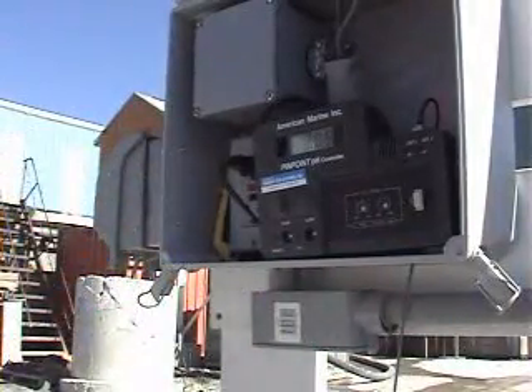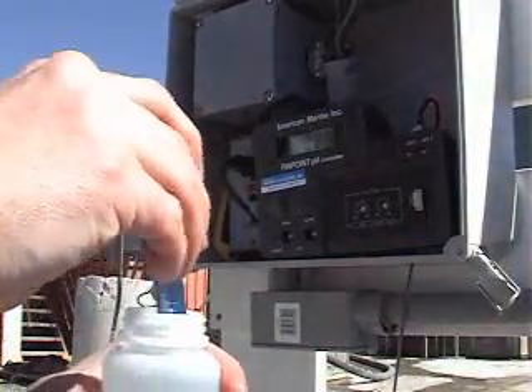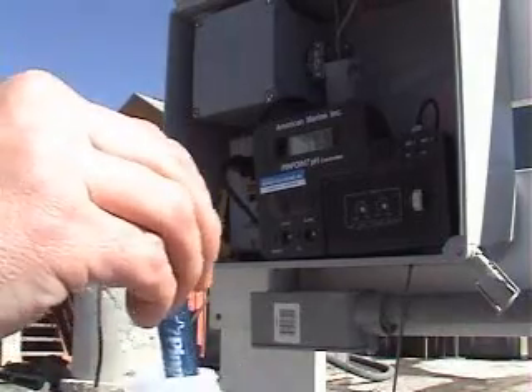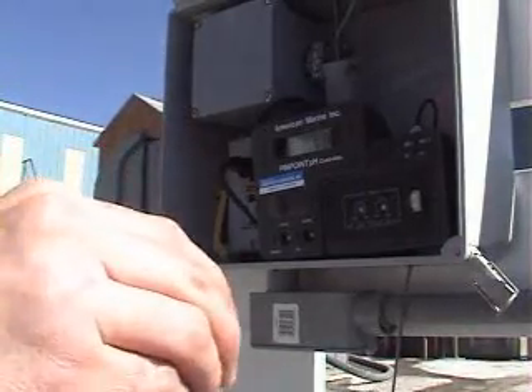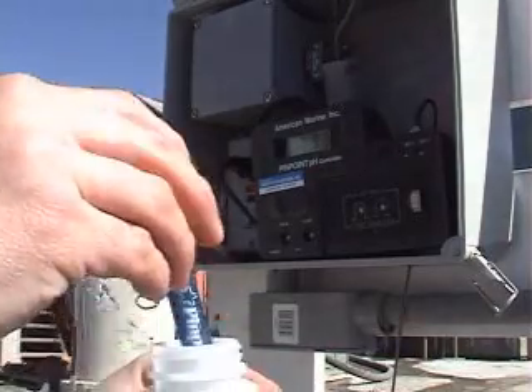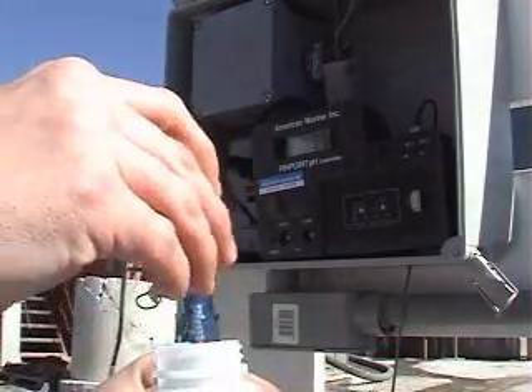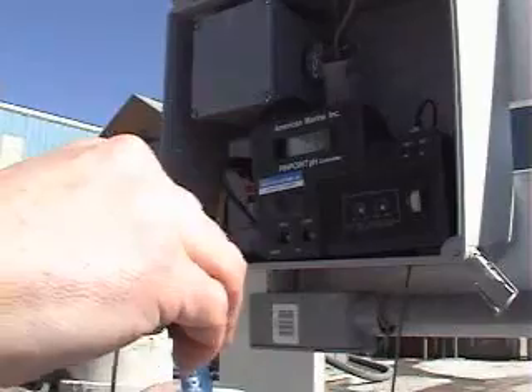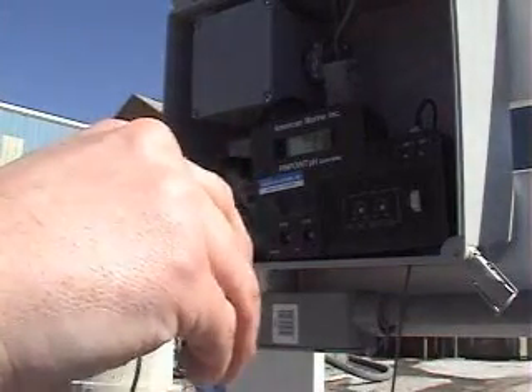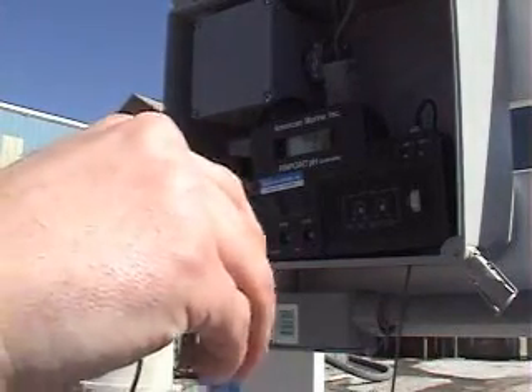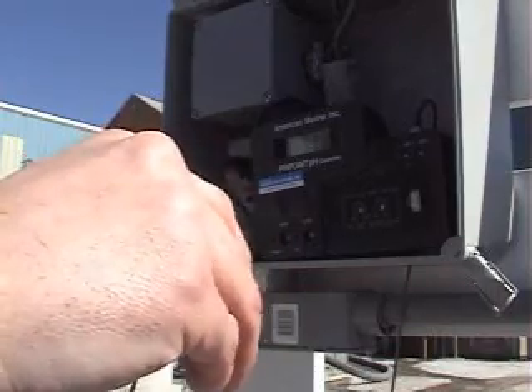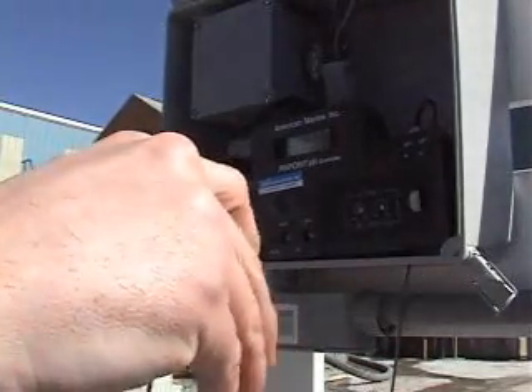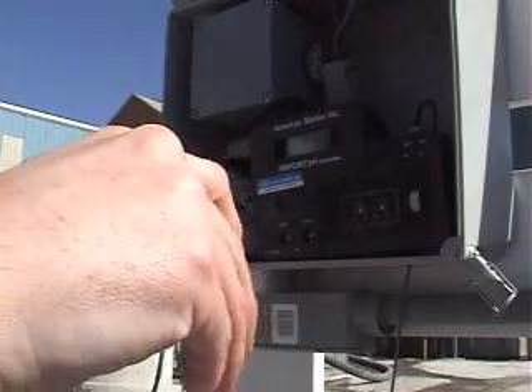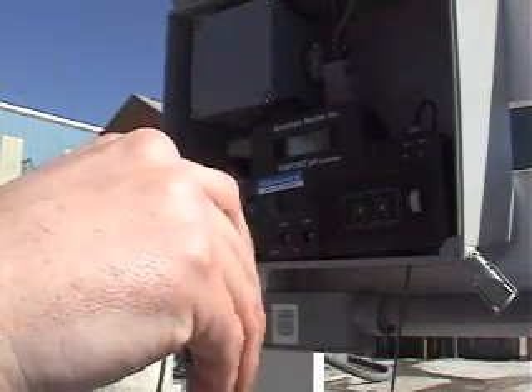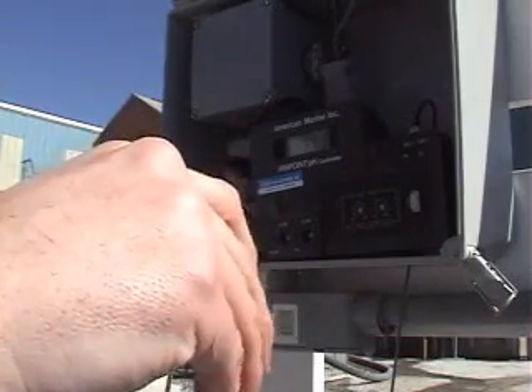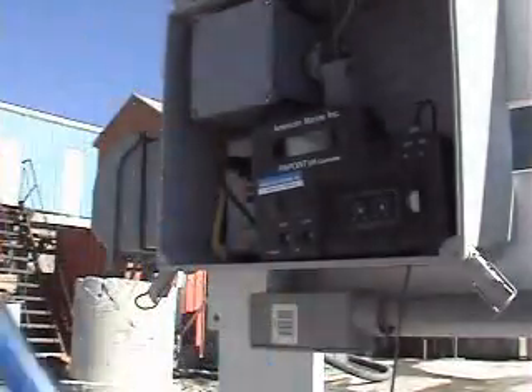Once I've done that, I'll take our diluted water and give it a quick swirl just to remove any of the cleaning solution. The cleaning solution has a very, very low pH, and it's important to always rinse the probe in some type of diluted water between transfers to different solutions. You certainly don't want to mix a low pH component like your cleaner with your 7 solution. Obviously, you won't get the proper calibration if your 7 solution is off.